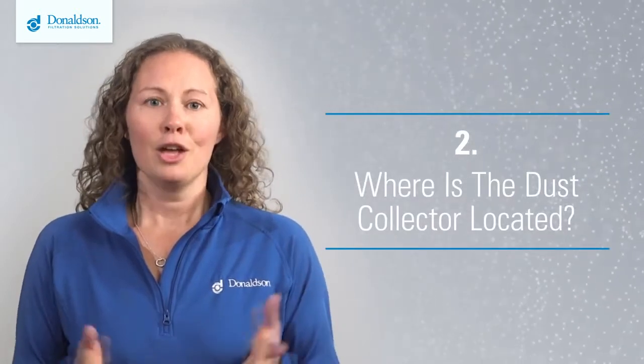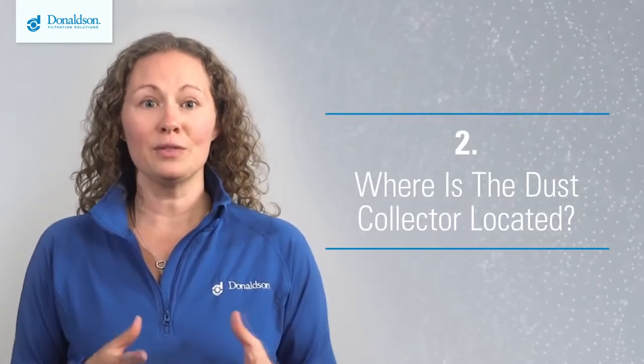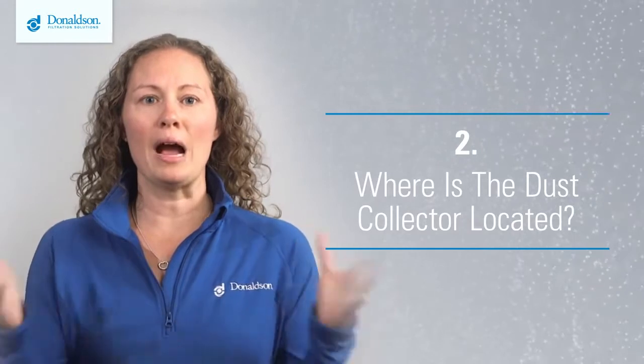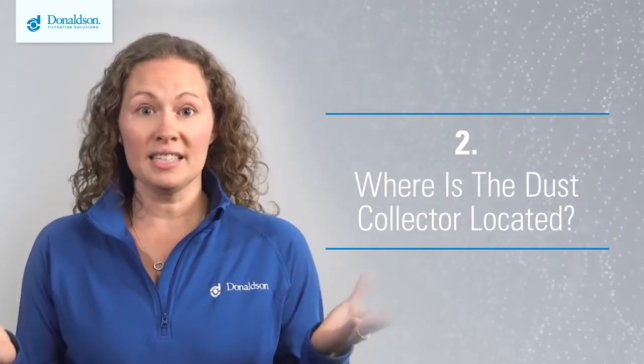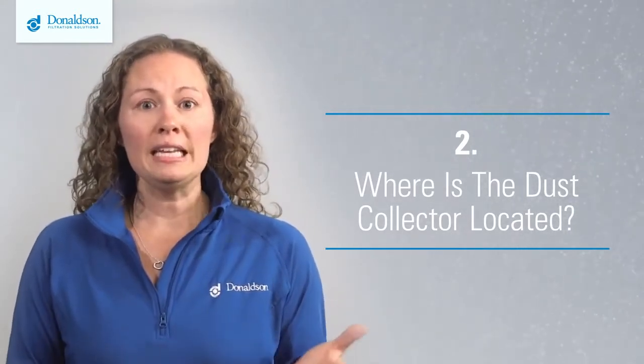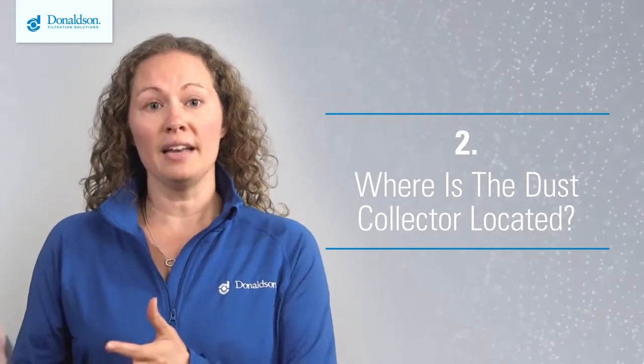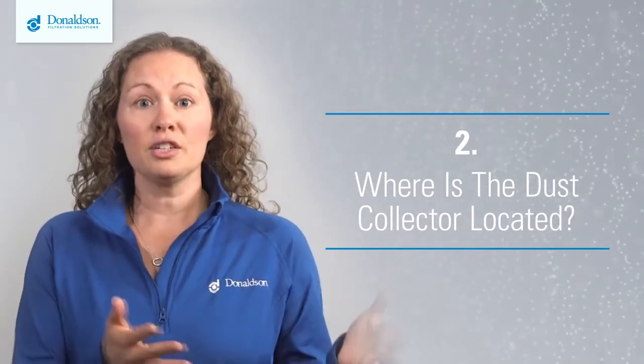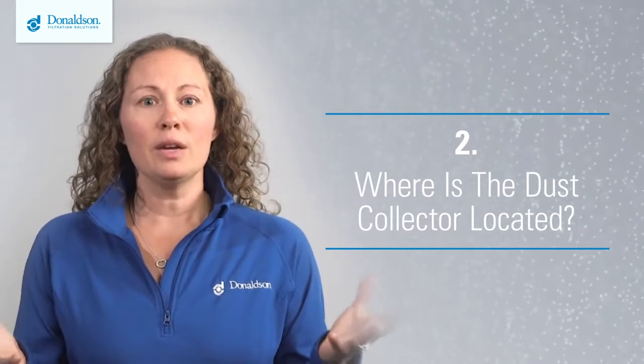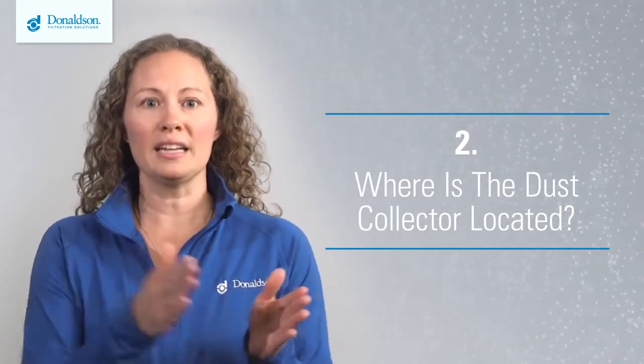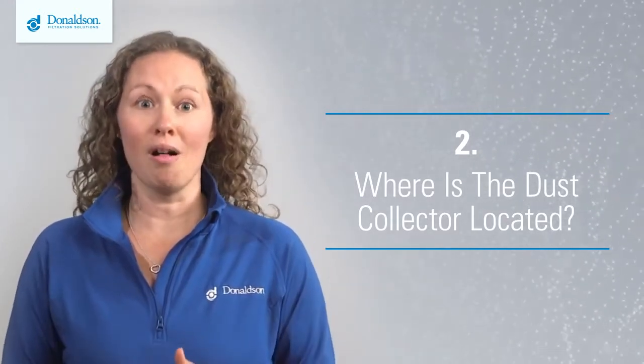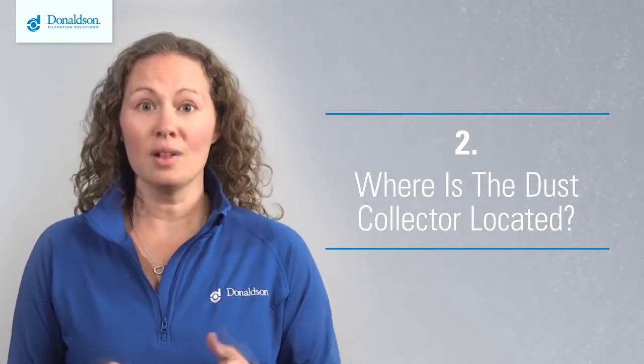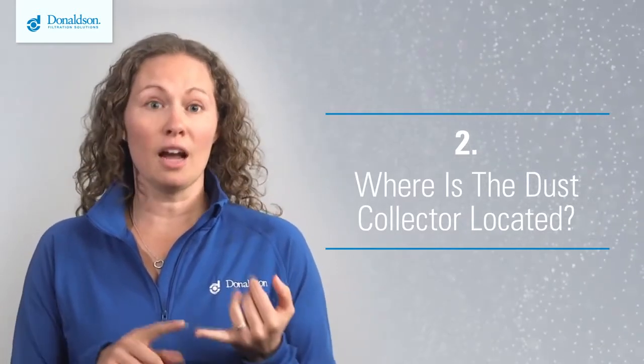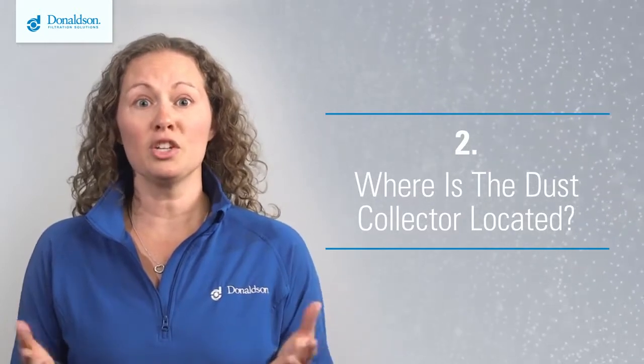Second, where is the dust collector located? Traditional explosion vents release flame and particulate into the area around the vent. If there isn't a safe location for this, you may need to locate the dust collector outside. Or, if the collector needs to be indoors, it may require additional ducting to direct the discharge through an exterior wall. If that's not possible, alternative strategies like a flameless vent or chemical suppression may need to be used.